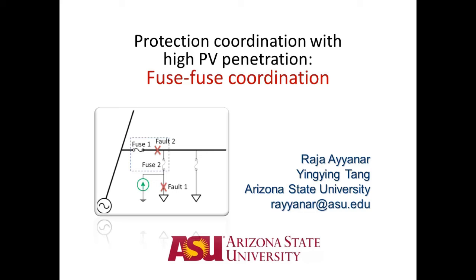This video focuses on the fuse-to-fuse coordination and describes automated methods to analyze the coordination of all the fuse-to-fuse combinations in the feeder under no PV and with PV scenarios.